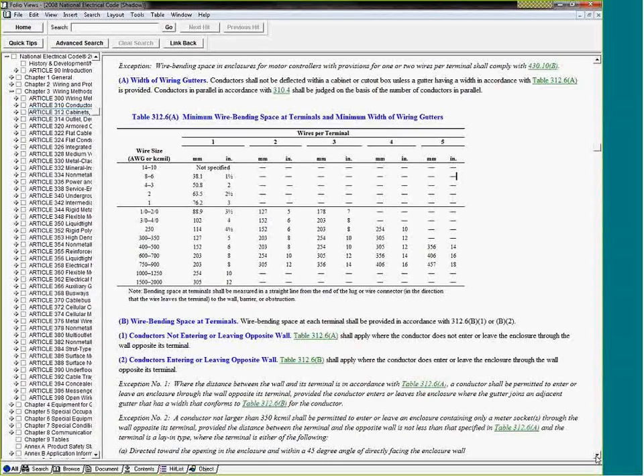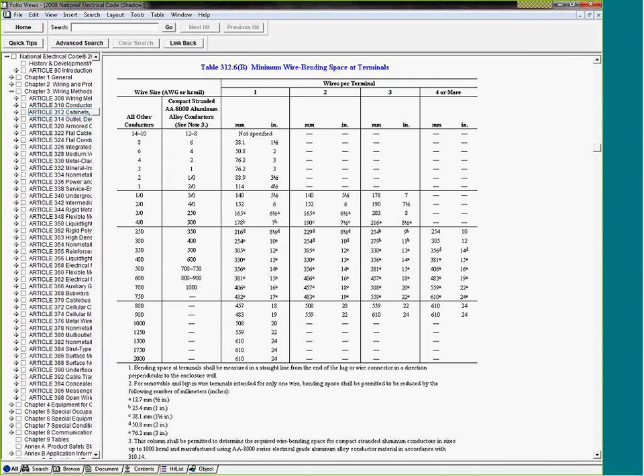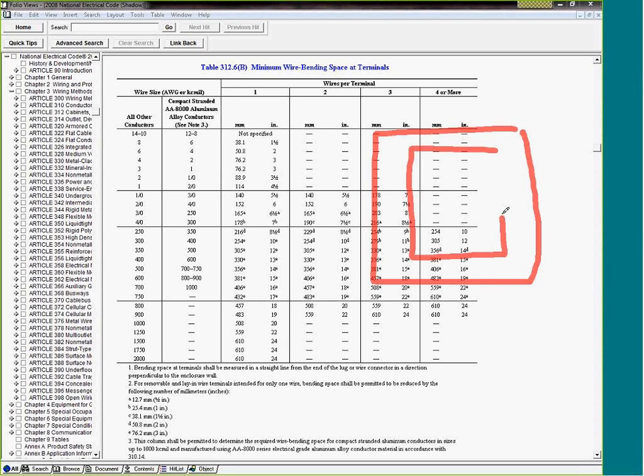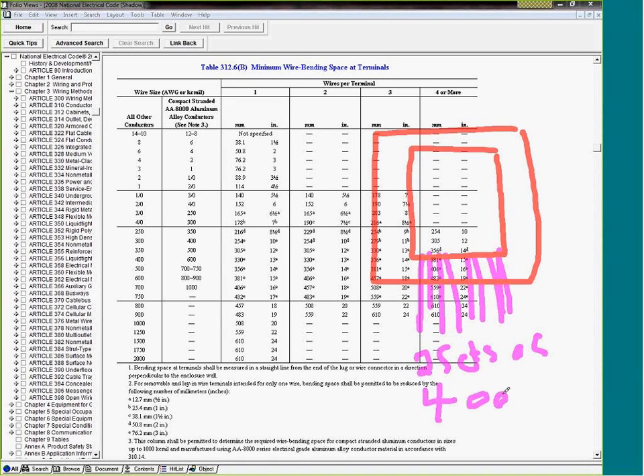This is B. Here's my table B. Here's my gutter, and I'm going to enter my box from the same side. Here is phase A, phase B, phase C, and I'm paralleling, and here's a neutral. So I have 2 sets. Let's parallel 2 sets of 400, either 4 conductors of 400. I decided to pull a full neutral.